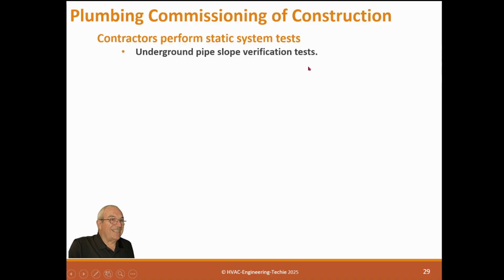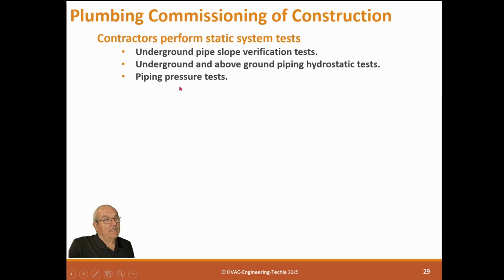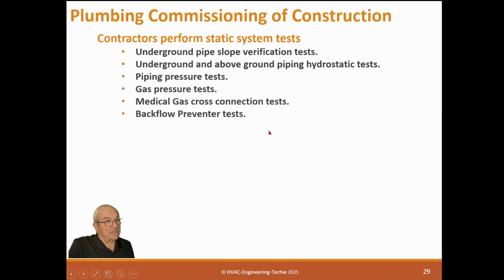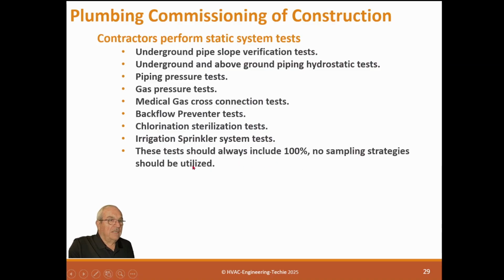Contractors perform static tests: underground pipe slope verification test, underground and above ground pipe hydrostatic test, piping pressure test, gas pressure test, medical gas cross-connection test, backflow preventer test, chlorination stabilization test, sterilization test, irrigation sprinkler system test. These tests should always include 100%; no sampling strategies should be utilized. Now, sampling strategy just means you want something to fail. So we want to test everything. And this is not hard to do.